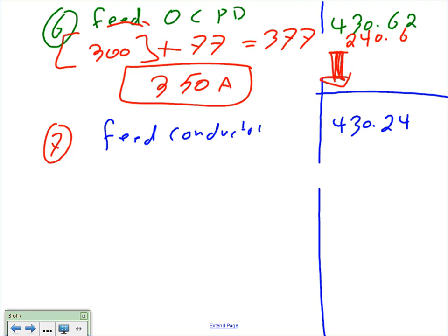Where did the 300 come from? That's the largest fuse in your system, right? Then you add to it the full load current of the second motor, and that will get you this number.